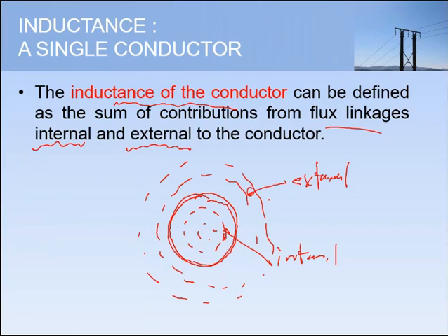For the external, there's a detailed calculation to this; it will be influenced by the other phase conductors. Once we have another conductor, it influences the external part. Internal, in most cases, is fixed. There's no difference, but the external is totally influenced by the cable beside that cable, if we have another cable sitting right beside this cable. But I'll just go through.